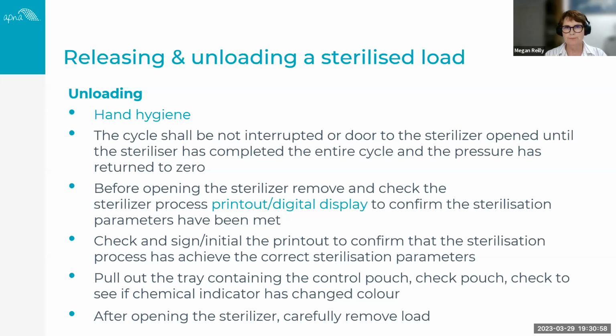If you have a printout, sign or initial that printout and have a log of names and signatures or initials so that it's easily identifiable. So what you're doing when you sign off, you're being accountable that the items have met all of the sterilization parameters. Make sure that when you pull out that tray, that you're looking at the pouches. If you use a control pouch, you're looking at the indicators, the external chemical indicator, to make sure that that has changed. Doesn't mean the item is sterilized. All it means is it's been subject to a sterilization process.